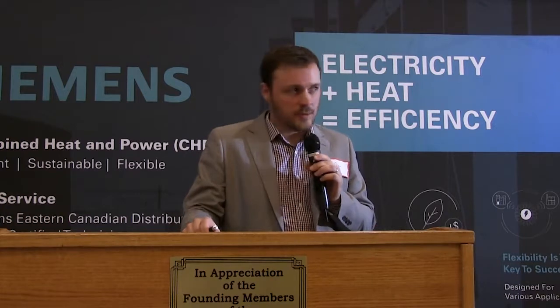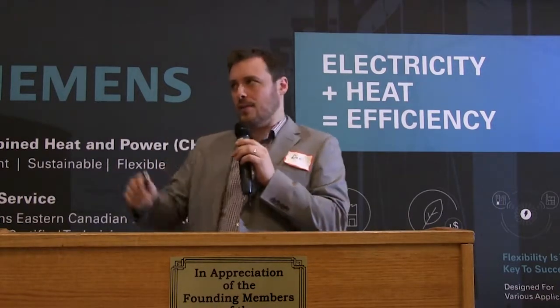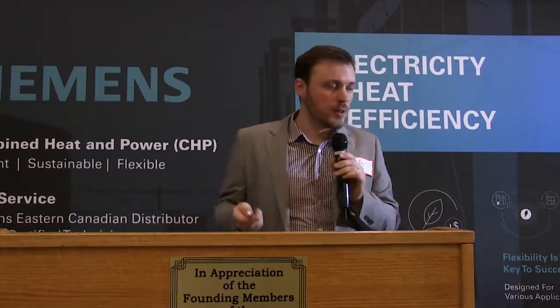What I'm building toward is an ROI calculator tool that will help you determine what return on investment you would get with one of these systems. On the electricity side, there are negligible capital costs in most cases for a standard grid setup — though we heard today that in some cases those can be quite high. Your operational costs are basically just what you're paying for hydro. On the co-generation side, you have the machine cost, building permits, electrical controls, connections, civil and mechanical work to set up the plant, plus maintenance and natural gas supply.